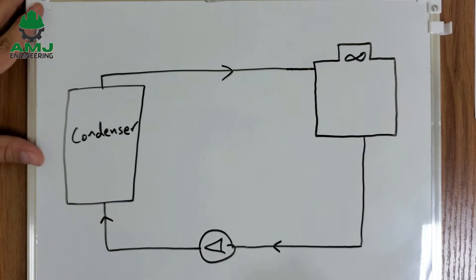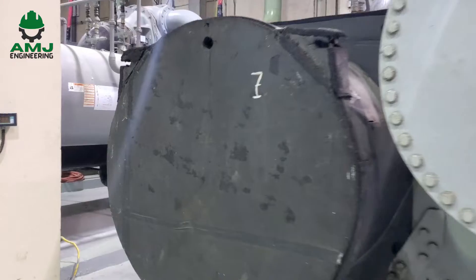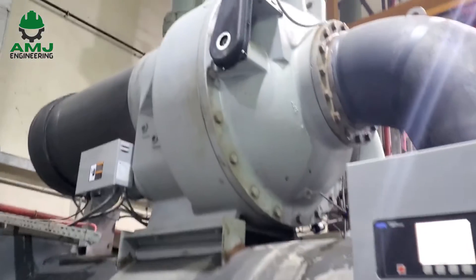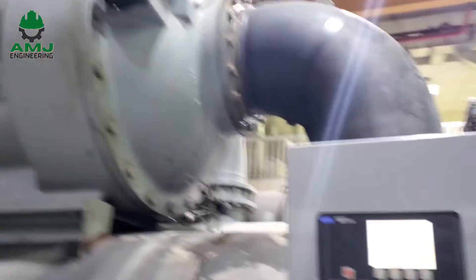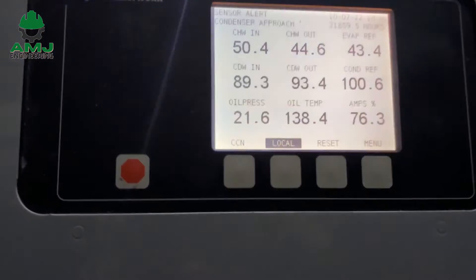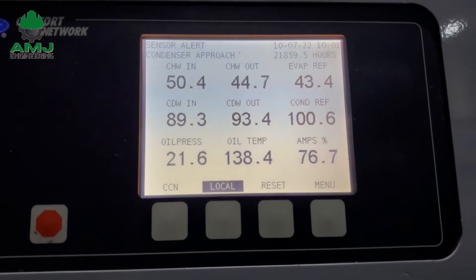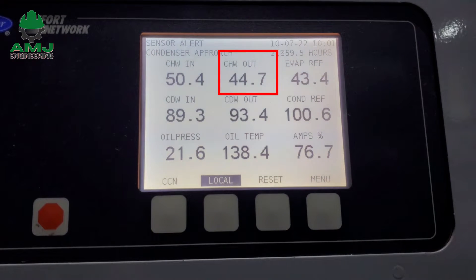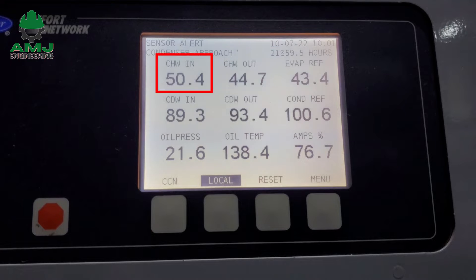What is the normal chiller evaporator approach? The chiller evaporator is responsible for chilled water supply and return. Inside the evaporator, the refrigerant absorbs heat from the chilled water, thereby cooling the chilled water and evaporating itself. Chilled water supply is the water leaving the chiller and entering the AHUs or FCUs, while chilled water return is the water leaving the AHUs or FCUs and entering the chiller.